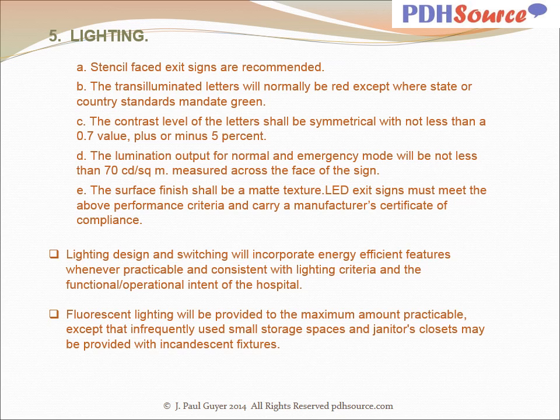Stencil-faced exit signs are recommended. The trans-illuminated letters will normally be red except where state or county standards mandate green. The contrast level of the letters shall be symmetrical with not less than a 0.7 value ±5%. The illumination output for normal and emergency mode will be not less than 70 measured across the face of the sign. The surface finish shall be a matte texture.